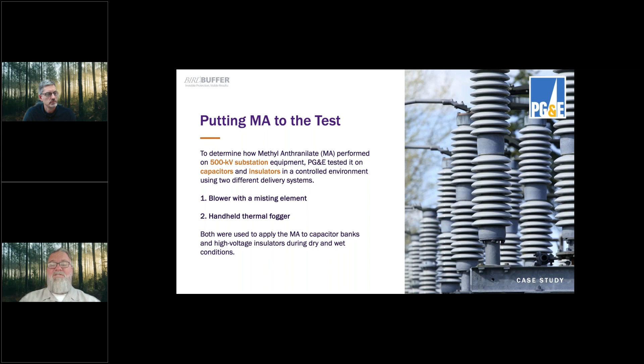That is the handheld thermal fogger that deploys a thick fog into the space with high doses of methyl anthranilate to pre-treat the area. Both were used to apply MA to capacitor banks and high voltage insulators during dry and wet conditions. So that's very interesting that they did it in dry and wet conditions as opposed to just one or the other. The results: electrical and chemical tests demonstrated that multiple applications did not jeopardize equipment. Direct spraying did not cause arcing or flashover.